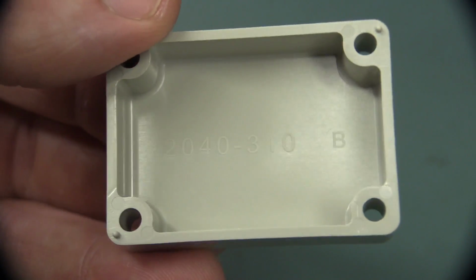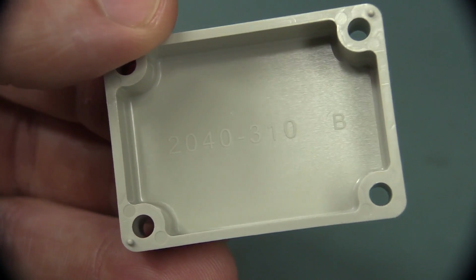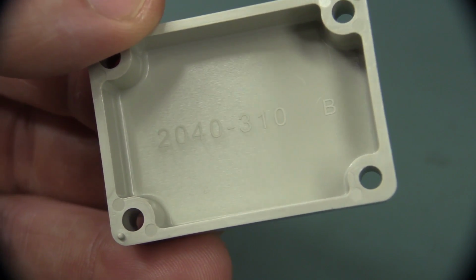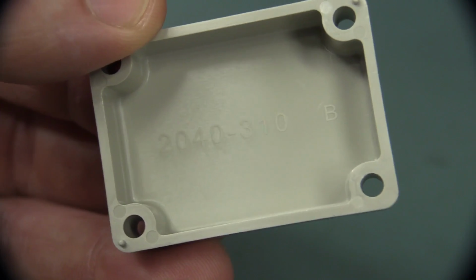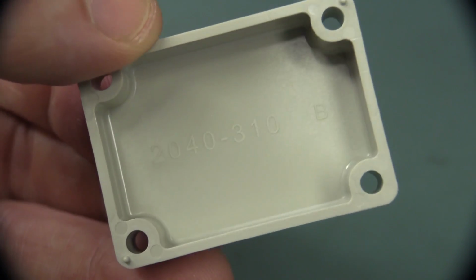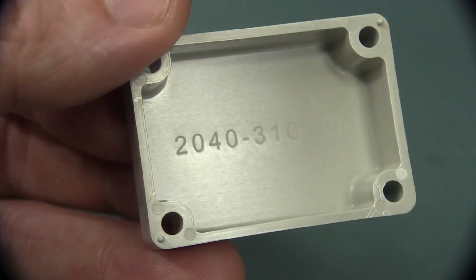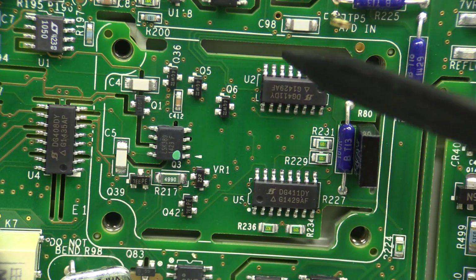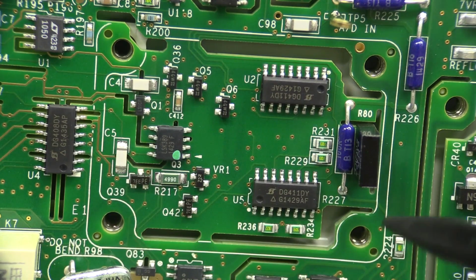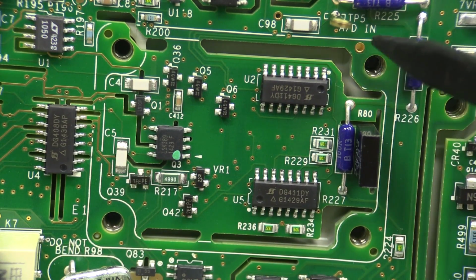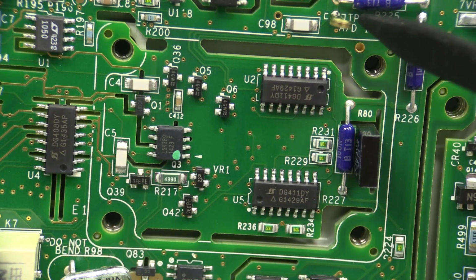The voltage reference does have its own internal heater, but still, you don't want the ambient changing willy-nilly based on the fan. You want it to change really gradually, and that's what putting a cover on it achieves. Here's what I think is possibly the ADC, because it's got that test point up here.